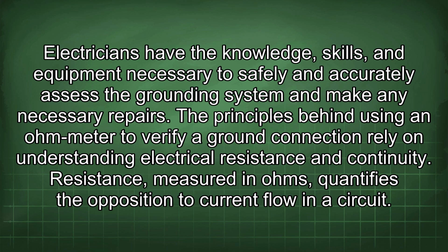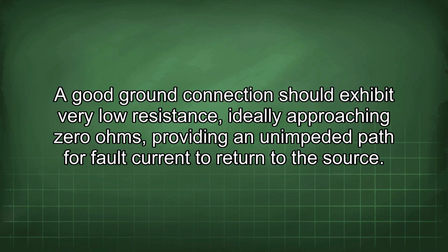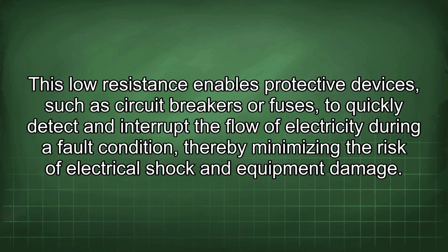The principles behind using an Ohm-Meter to verify a ground connection rely on understanding electrical resistance and continuity. Resistance, measured in ohms, quantifies the opposition to current flow in a circuit. A good ground connection should exhibit very low resistance, ideally approaching 0 ohms, providing an unimpeded path for fault current to return to the source. This low resistance enables protective devices, such as circuit breakers or fuses, to quickly detect and interrupt the flow of electricity during a fault condition, thereby minimizing the risk of electrical shock and equipment damage.